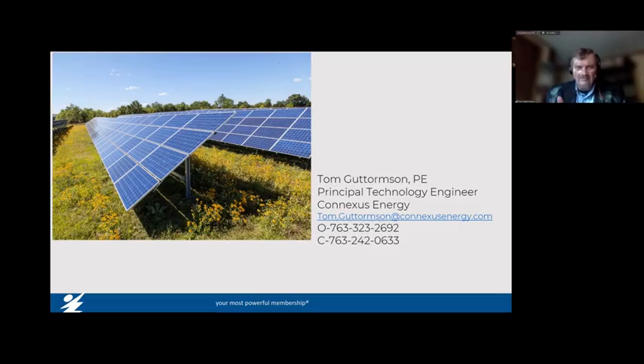We have a commitment to NextEra to charge from solar for our demand reduction program, and also to Great River Energy, so if we ever do grid charge, we let them know we're going to do this. Then when we're done, we make sure and discharge all the grid stored energy and recharge it back from solar, and then we're contractually whole. So yeah, grid charging, we can certainly do that. If there was a use case where we could charge from the grid in the morning when prices are cheap, and discharge again in the afternoon when capacity prices are high to do some energy arbitrage, the batteries would be fully capable of that use case.